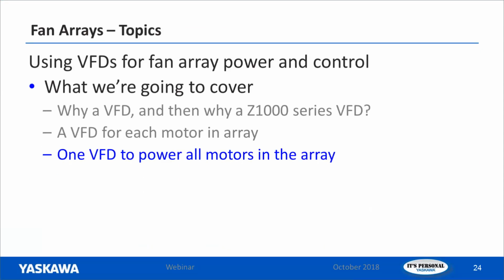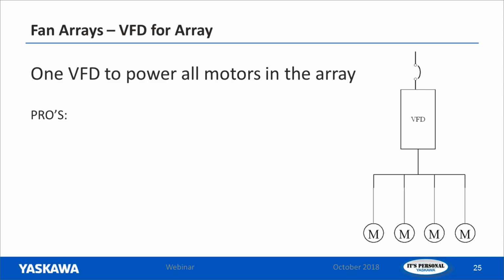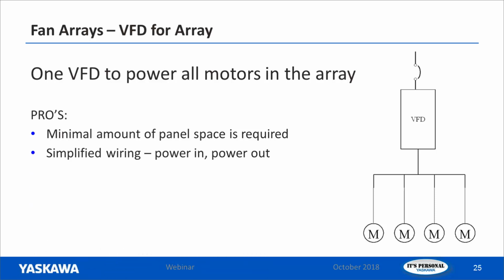Alright, so let's move on to looking at using one VFD to power all the motors in the array. And over here on the right, we've got a depiction of the same 4-motor array, but now we've got one VFD powering it. One advantage, of course, is now you're minimizing the amount of panel space that's required for the VFD. Simplified wiring, you get your power in, power out. You can share the same conduit out to those motors from the one output of the VFD.